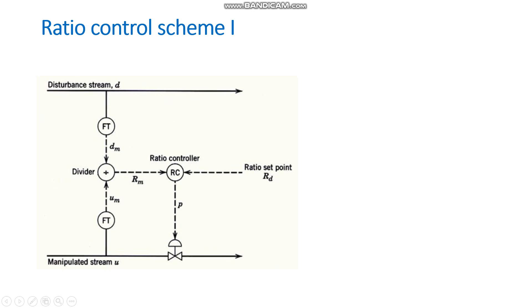In scheme one, a ratio set point is given to the system. The disturbance stream — also called the wild stream — and the manipulated stream are the two flows. Flow transmitters are placed on the flow lines, and a control valve is placed on the controllable flow line. The ratio is maintained by manipulating this flow using the control valve.